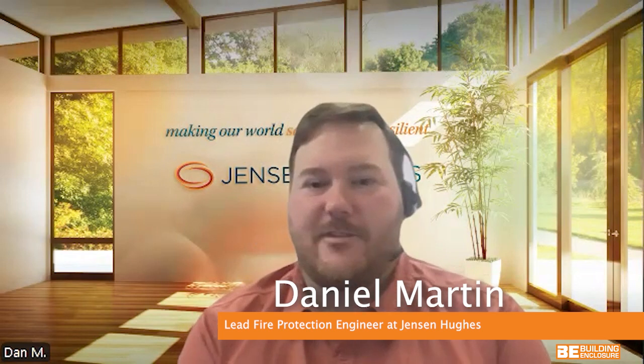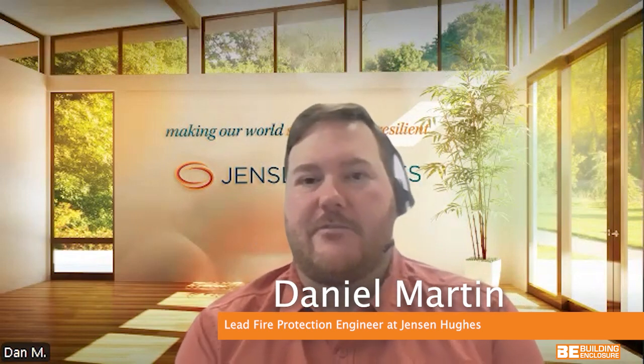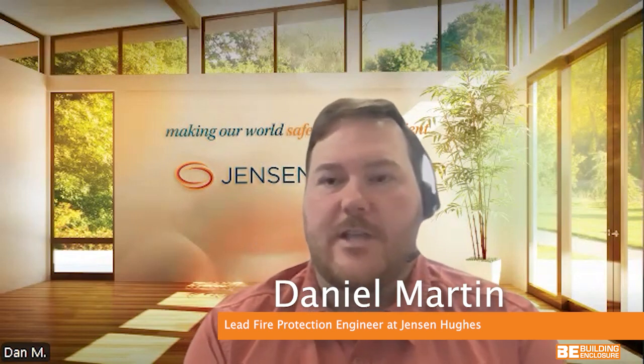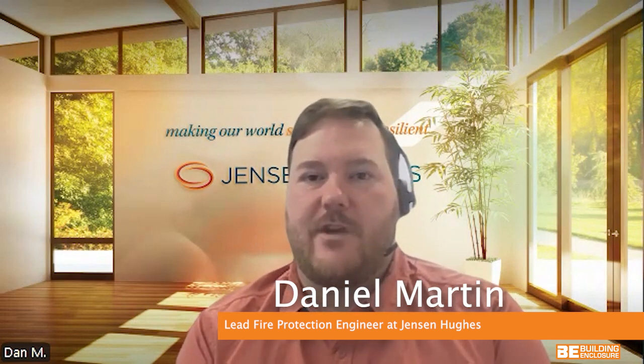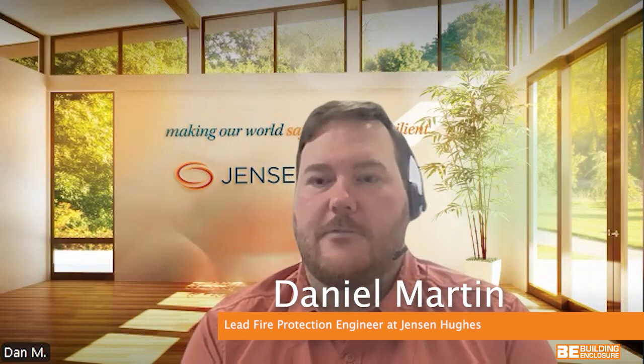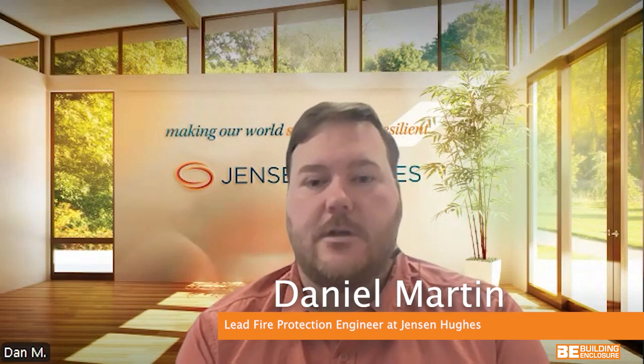So to start off, can you go over what the NFPA 285 analysis involves? It's a very loaded question. Yes. There are different types of analyses that you can run with NFPA 285. Obviously, any analysis that you do with NFPA 285 needs to start with a compliant tested assembly. From there, we can get into generic engineering analyses, what we call our build-a-wall analyses, where you have a table of compliant configurations that you can build together.